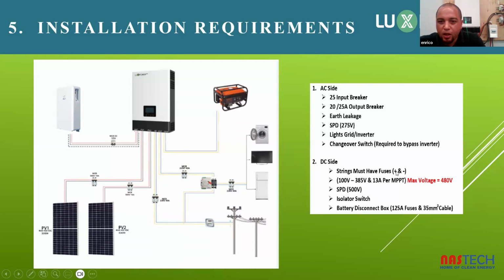On the DC side, the strings must have positive and negative fuses. This is the solar panels with a PV range of 100 volts to 385 volts. Here's the 13 amp MPPT. The surge protection device that you put on the DC side of the solar panels is 500 volt. This is according to standard, because the maximum voltage that the machine can take is about 480 volt. A battery isolator is required and a battery disconnect box.